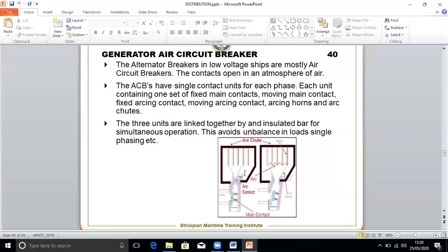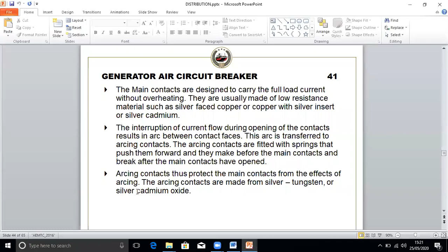The main contacts are designed to carry the full load current without overheating. They are usually made of low resistance materials such as silver faced copper or copper with silver. Interruption of the current flow during the opening of the contacts results in an arc between the contact faces. The arc is transferred to the arcing contacts. Arcing contacts are fitted with springs that push them forward and make them before the main contacts and break after the main contacts are open. Arcing contacts thus protect the main contacts from the effects of arcing. Arcing contacts are made from silver, tungsten, or silver cadmium.